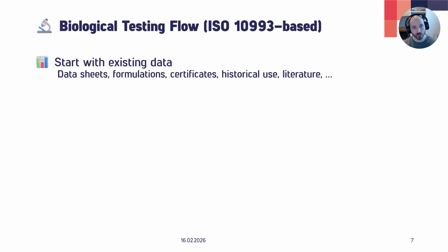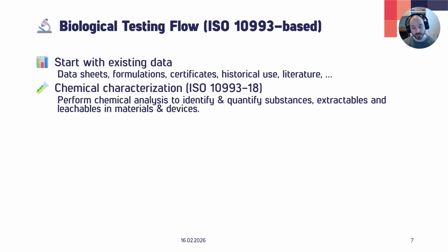And how should we do that? So we start with the existing data. We gather data sheets, we gather formulations, if we can get them from the manufacturer. We gather certifications, historical uses of this material, sometimes literature, and sometimes they might even have test reports. And then, if that's not enough, we start doing chemical characterization according to ISO 10993-18. This is the chemical characterization part of the ISO 10993 series. And we perform this chemical analysis and quantify substances, extractables, leachables, in the materials and devices.